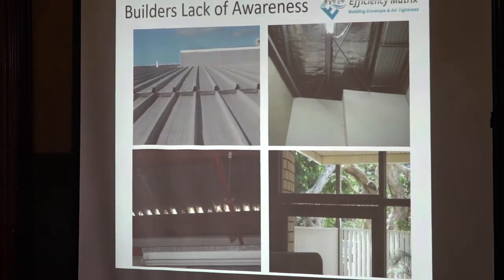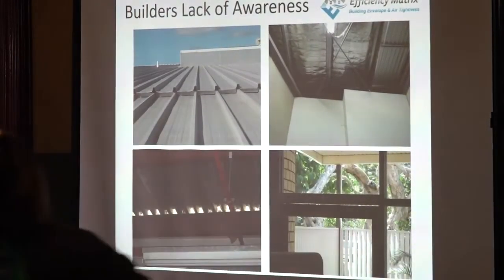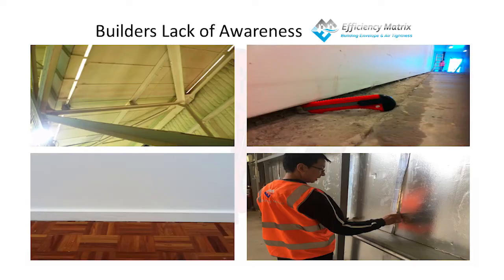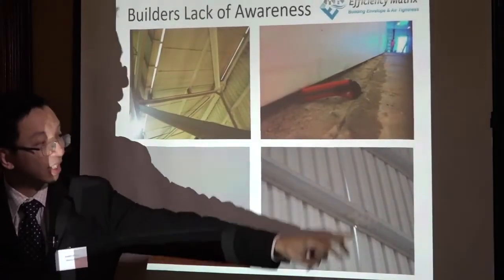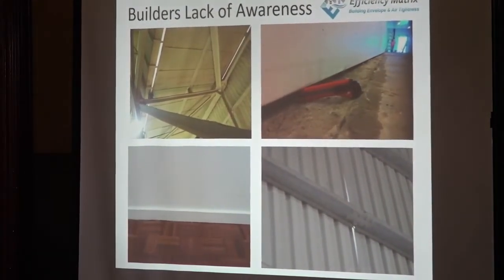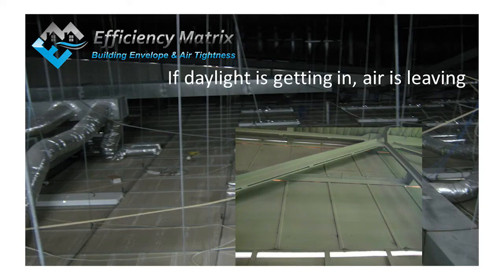Do you think the air will follow our arrows in the drawings? As Sam, Mark, and Stuart said — air is unruly; it never follows our arrows. Common problems include gaps and cracks, plasterboard not touching the slab, uncaulked skirting boards, steel panels slightly bent that no one bothers to tape or seal. When you can see daylight coming through, of course air is coming in.